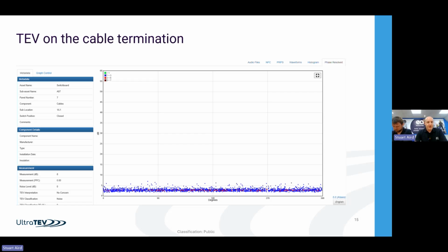Just as a note as well, on this particular cable circuit, we did take a TEV measurement of the cable termination, and we can see that there's no evidence of partial discharge with that TEV measurement. Because the discharge is 66%, so you're talking 600-700 meters along that cable route, we're not picking up anything with a transient earth voltage sensor on the cable termination. The signal by the time it gets to us is not in the frequency range of the transient earth voltage. So for this particular circuit, we didn't see any PD in that measurement, but only on the HFCT.